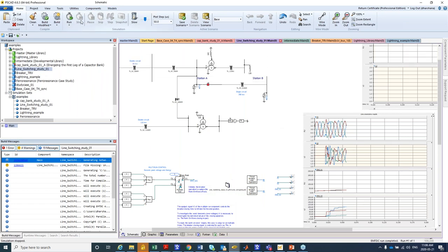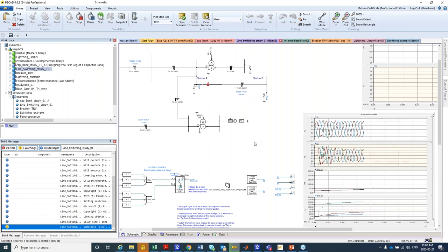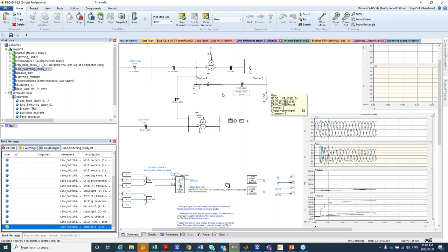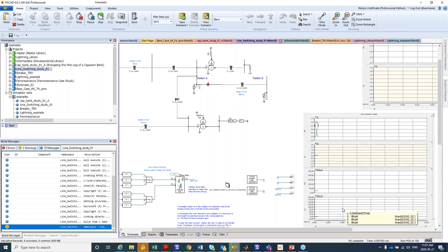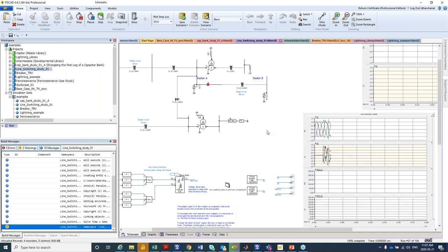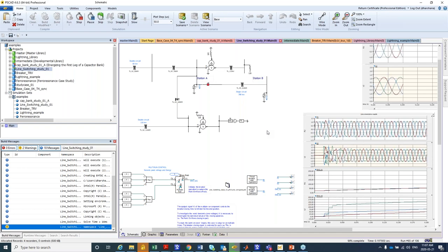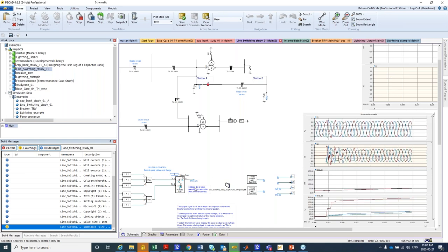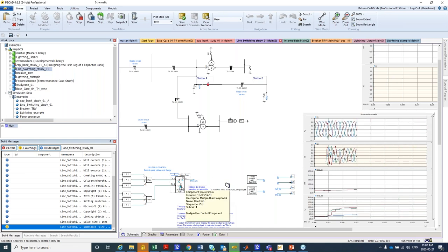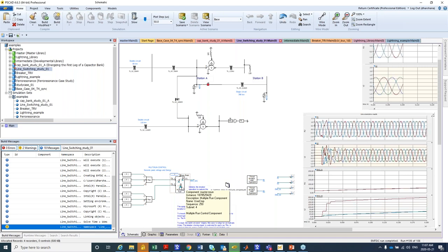This is an example of transmission line switching. I close the breaker at station A to observe the over-voltages appearing at station A and station B, and also the surge arrester energy dissipation. In a line switching study, you want to verify whether the surge arresters can limit the over-voltage, and whether the over-voltage is well enough damped that the arrester does not absorb more energy than it is capable of. This case uses PSCAD's multiple-run component, running a parametric study by changing the point-on-wave to capture the worst case.